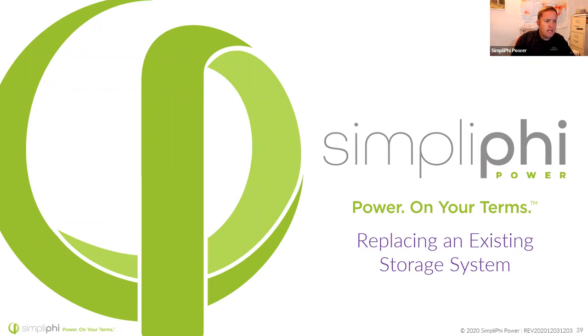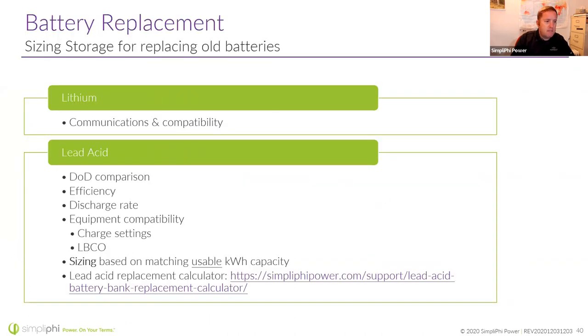When replacing old batteries, some older off-grid equipment can't use the modern communications available on new batteries. That's why we make both a standard PHI battery — which has a simpler internal analog battery management system with no digital communications — and the Amplify battery, which has digital communications. There's no reason to buy the more expensive Amplify if the site equipment can't communicate; the standard PHI has the same chemistry and same form factor of cylindrical cells. Check our website for calculators — you tell it what you have and it'll tell you what you need in our new batteries.